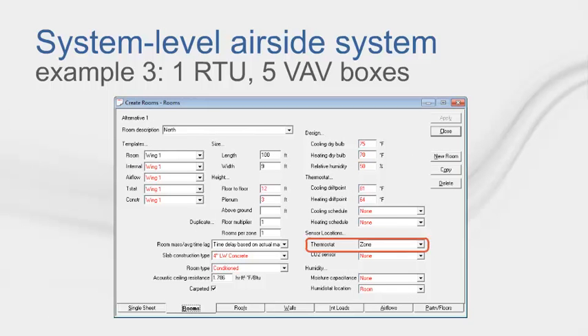By setting the thermostat location to zone back in the Create Room section on the Rooms tab, the program, during energy calculations, is pulling all the rooms on this VAV box to come up with the operating mode for the terminal device. Only rooms that have zone will be pulled. If the room is in the zone but does not contribute to the thermostat reading, its thermostat location should be specified as None.